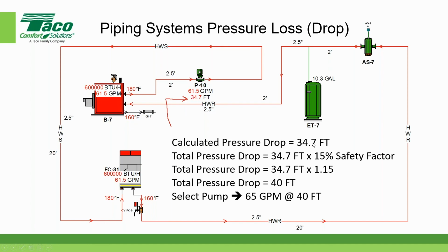So the software calculated the same pressure drop as I did manually, and that's because I used the same procedures in the software that I used for my manual calculation. The benefit of doing this using software is that the diagram can become much more sophisticated and have many more components. You can see I oversimplified this so that I could demonstrate how to do a manual calculation. But if I had 30 or 40 valves in it, or multiple pieces of equipment, or 10 or 15 different circuits, the calculation would be very complex. The nice feature about using software is that it can keep track of all this. But behind the scenes, the software is just doing the same exact thing that I did manually, only automated.